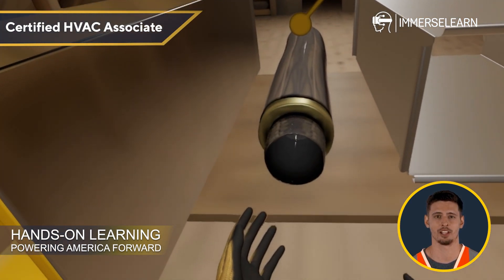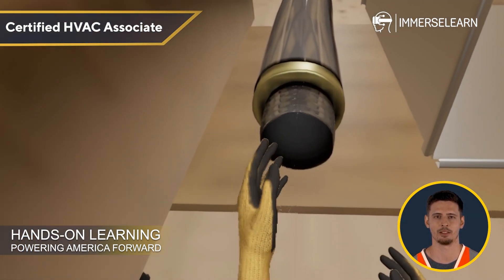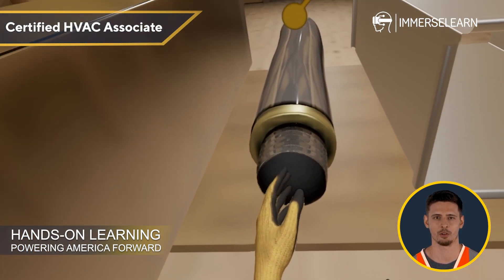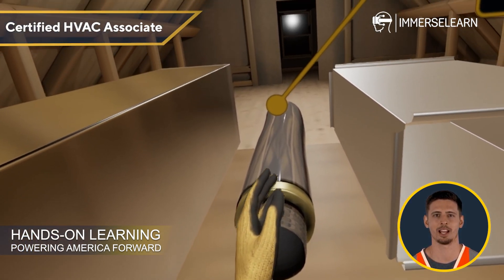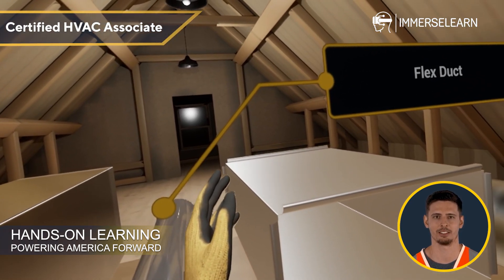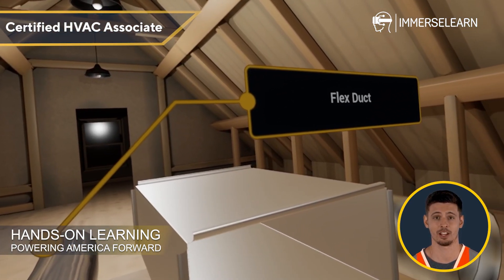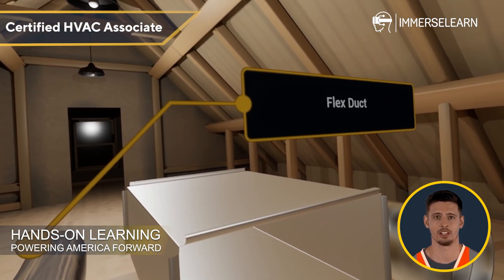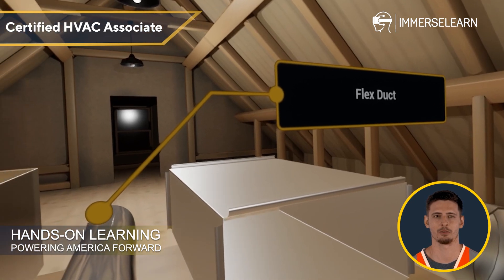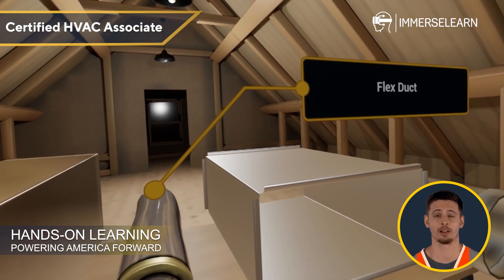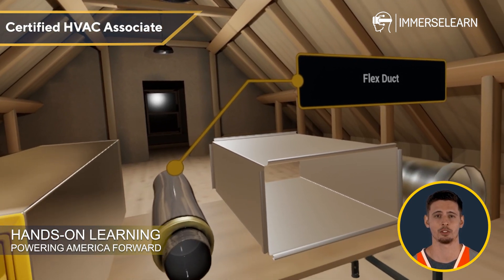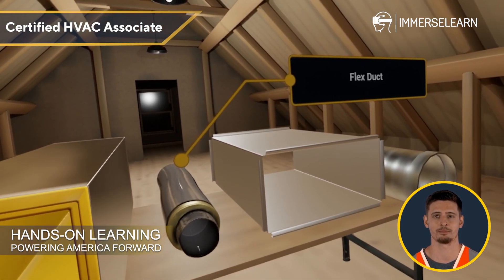Now, let's check out flex duct. This lightweight option is made from a wire coil wrapped in a plastic liner and insulation. It's incredibly easy to install and perfect for maneuvering through tight spaces. But be careful — too many bends or improper installation can restrict airflow and reduce efficiency.